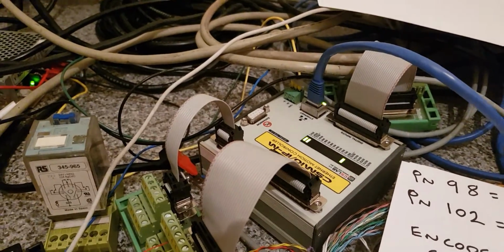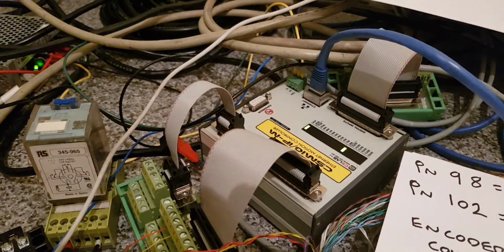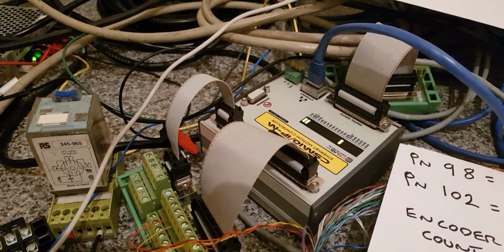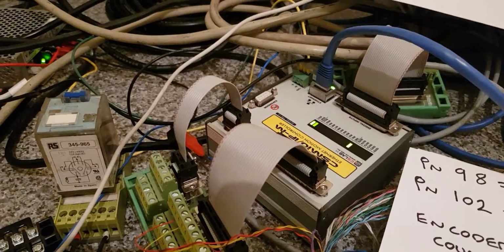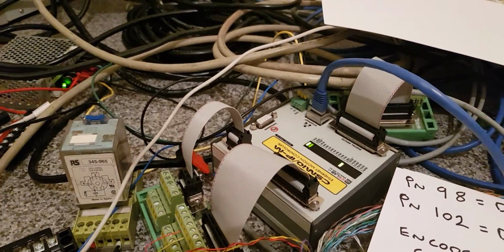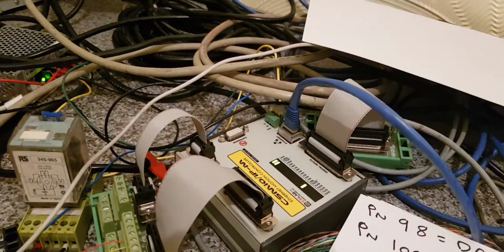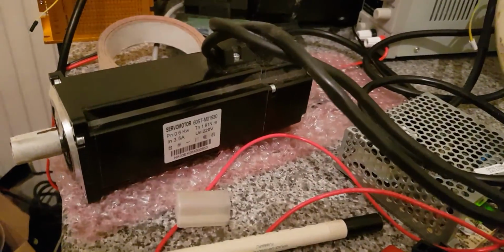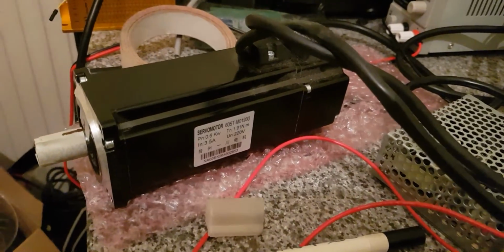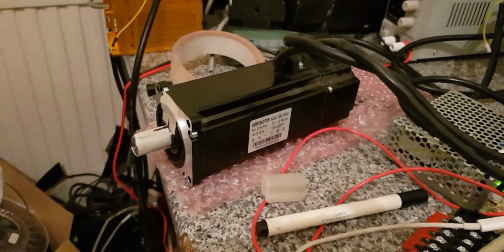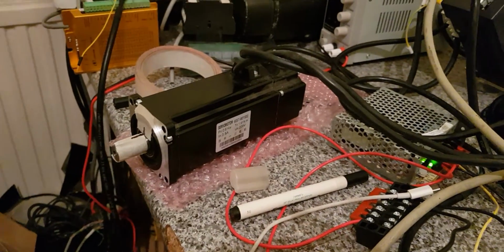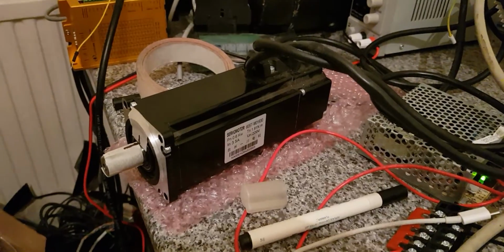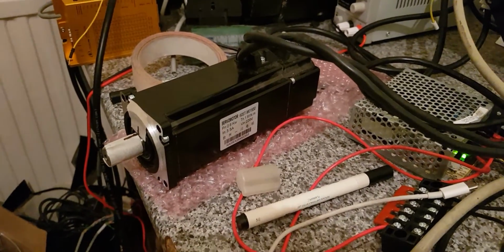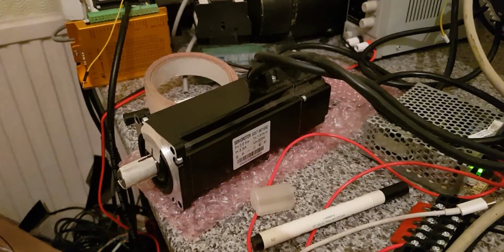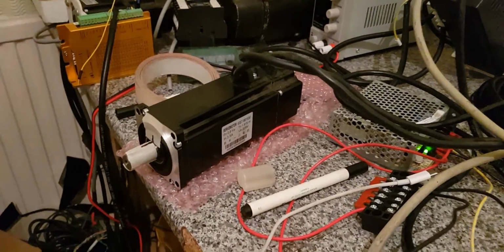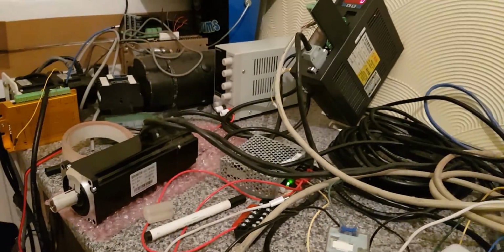A stepper drive, you rarely set a stepper drive up at 2,000. So you're more than equivalent to a stepper, but you've got twice the speed, twice the torque. Well, a lot more torque, because servo motors, the 1.9 newton meters that this motor is, that's constant across its speed. So you're getting 1.9 newton meters at 3000 RPM. Stepper motor won't even do 3000 RPM. And even at 1500 RPM, if you got it to do that, you'd be lucky if you've got 0.2 of a newton meter left, you have nothing. So you can see the advantage of them.